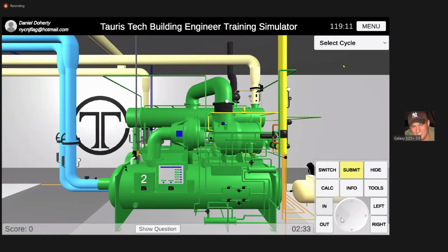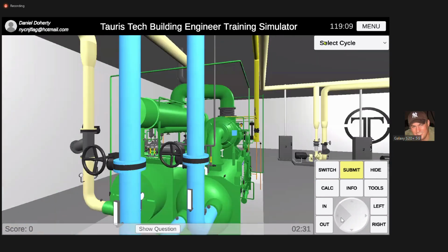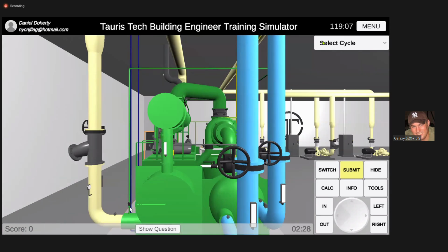All right. So now the last cycle is the oil cooling cycle. The oil cooling cycle starts right here on my screen. It taps into the condenser water. It has a shut-off valve right here. So if you want to shut off the cooling water for the oil cycle, you would shut it off right there. That little valve right there.